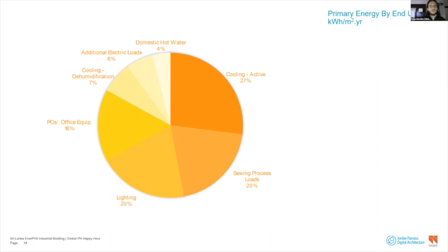So one of the things we looked at is, because there's such a high dehumidification load in this climate and in this building particularly, cooling and the strategies to not only cool but also dehumidify are a huge part of the building's energy demand. And in a typical cooling system, when you want to really dehumidify air, you have to super cool that air and condense all of that moisture out, so the moisture in the air can condense on the coils, and then reheat that air. So you're doing a lot of reheat.